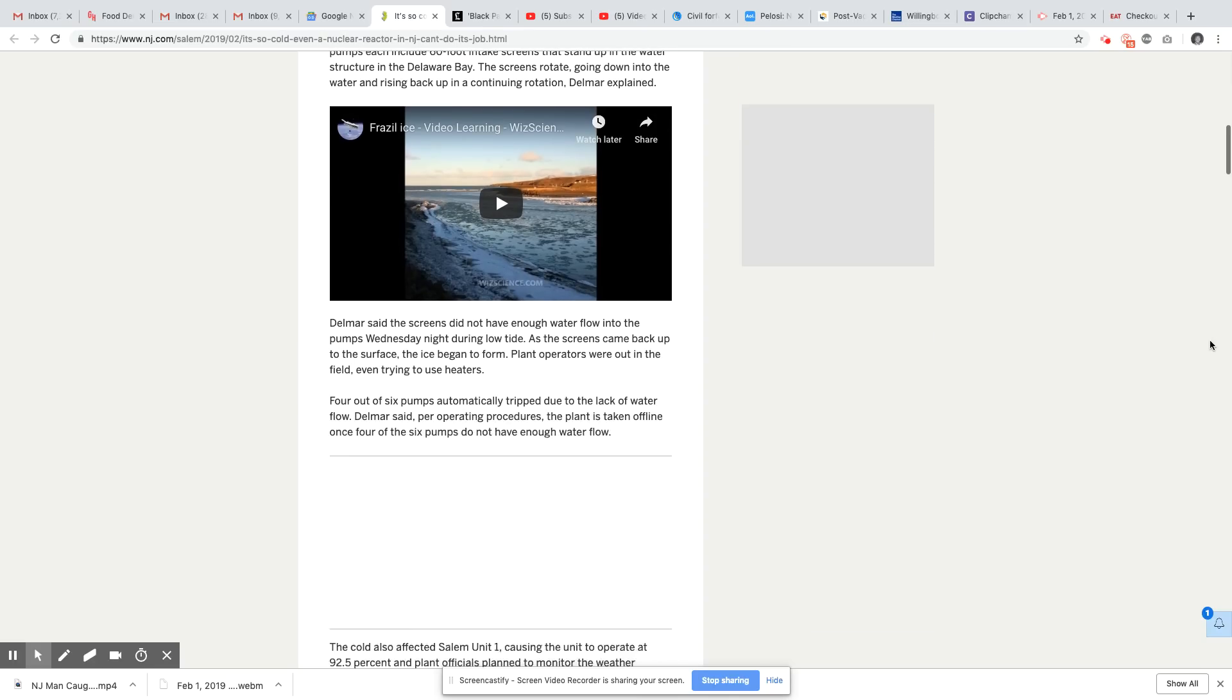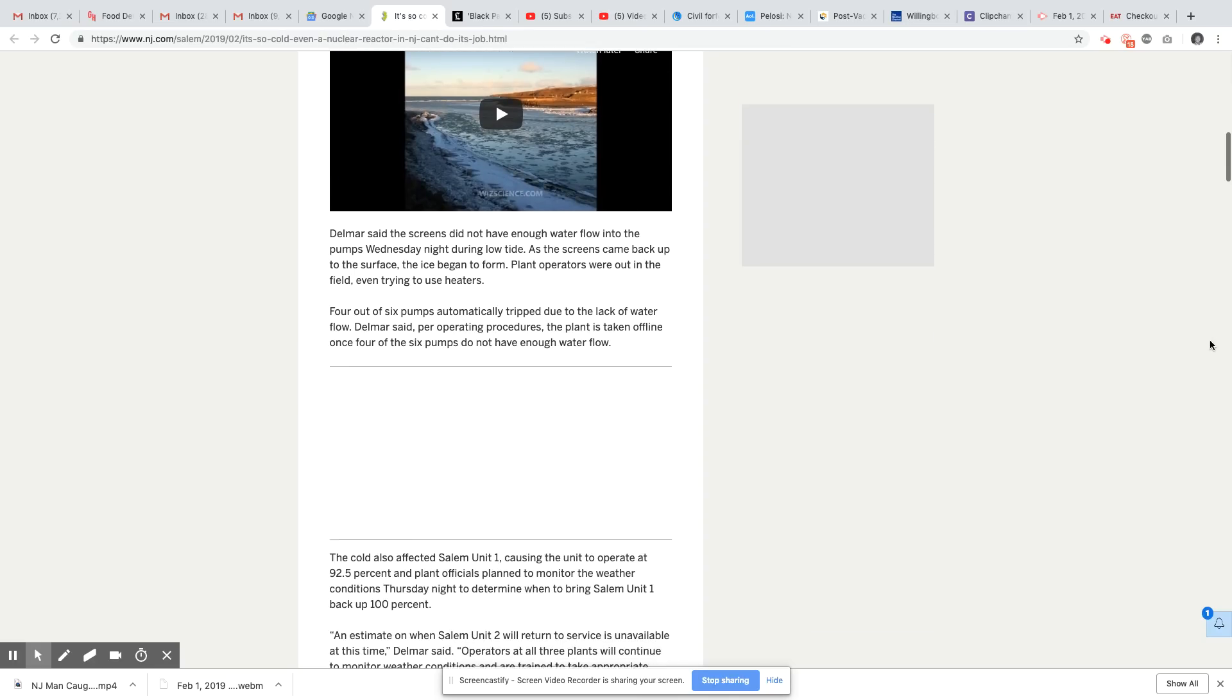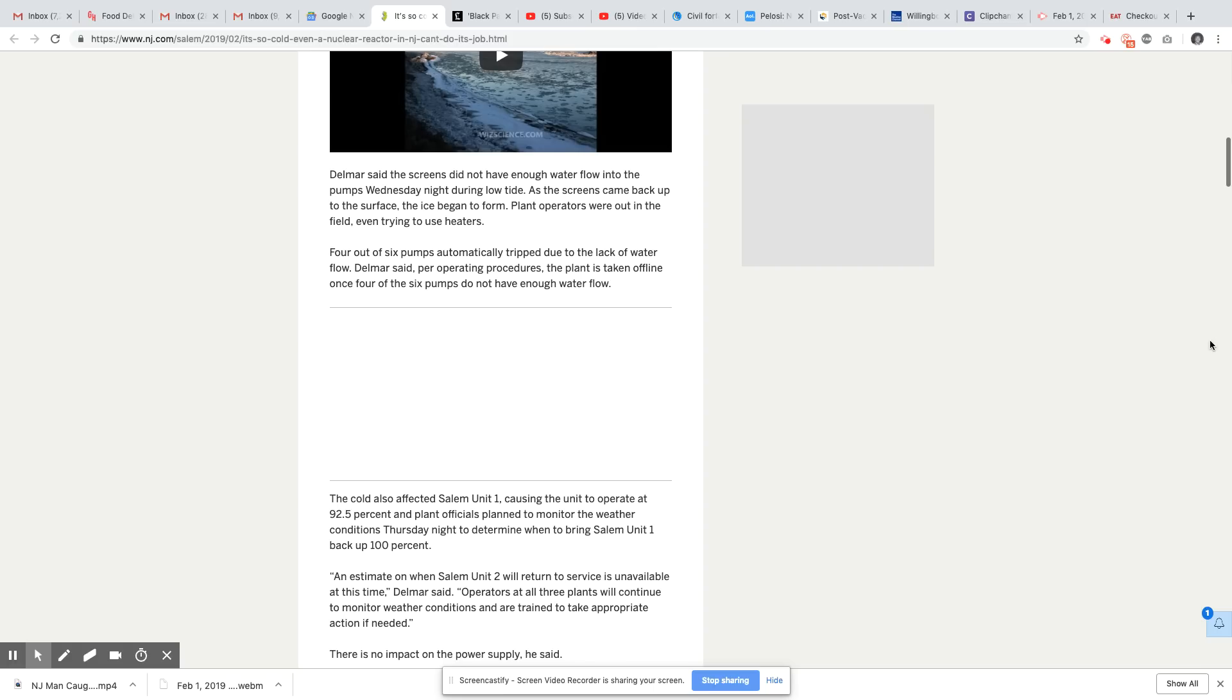Delmar said the screens did not have enough water flow into the pumps Wednesday night during low tide. As the screens came back up to the surface, the ice began to form. The plant operators were out in the field, even trying to use heaters. Four out of six pumps automatically tripped due to the lack of water flow. Yeah, everything was frozen, Delmar said. Per operated procedures, the plant is taken offline once four of the six pumps do not have enough water flow.